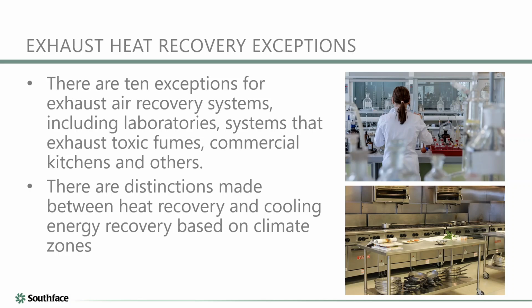And there's a reason for that. From an equipment standpoint, most of these buildings that are specialized, talking about CDC, hospitals, stuff like that, have special requirements for a certain amount of air for a process or some function that has to come in. So that air has to move at that rate and nothing else. That takes precedence over recovering energy. Basically, that's what it is.